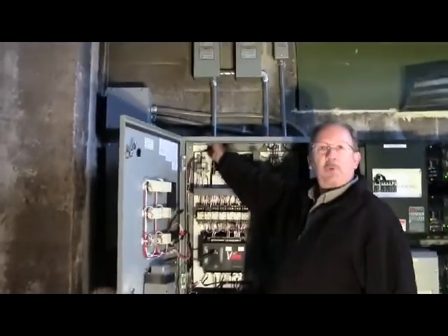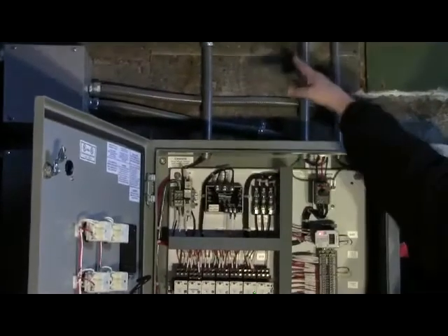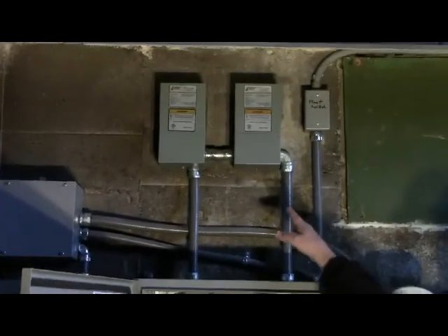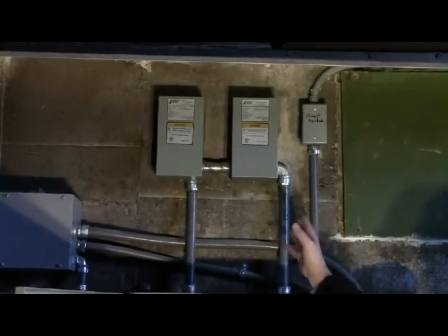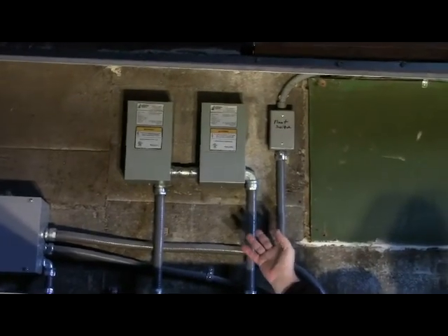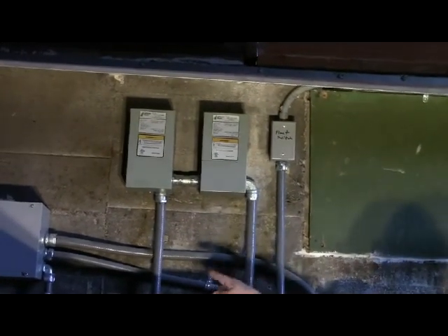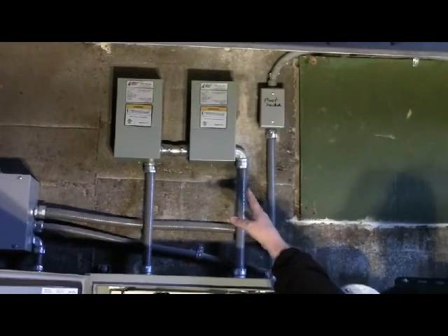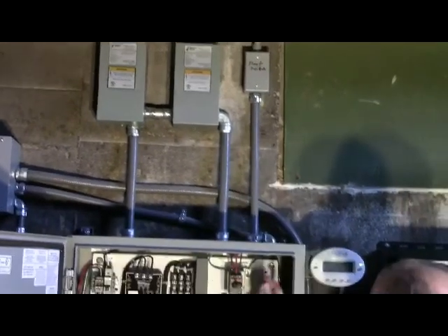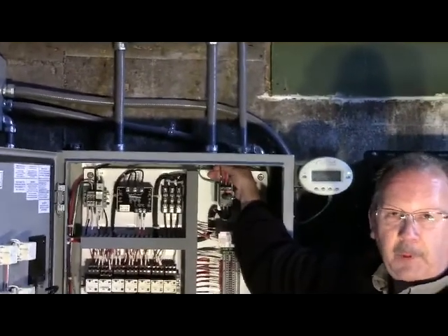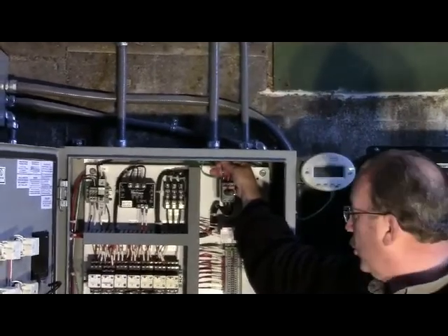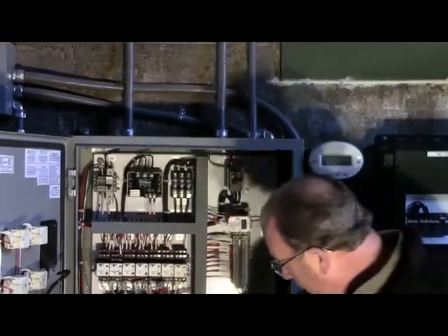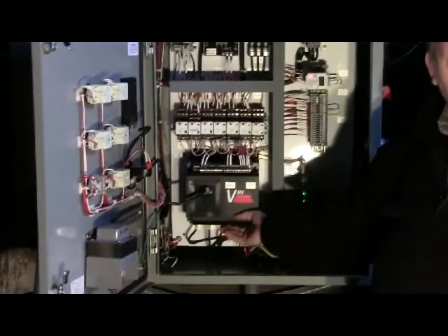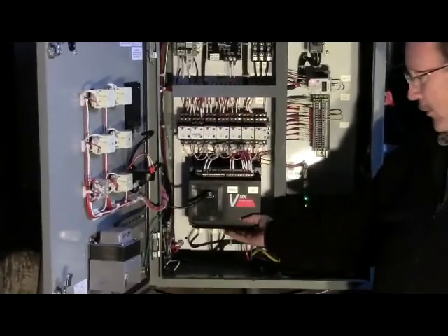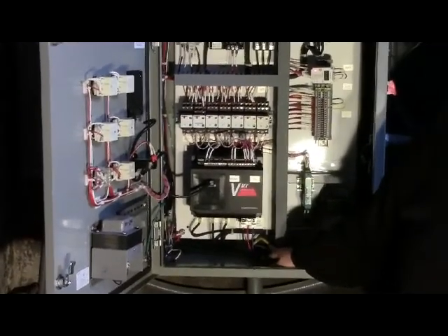That's a black, red, and a blue. We're going up to my buck-boost transformers, and here I chose to use an open delta system because that's all I needed, and the transformers were plenty big. The 208 comes up, goes through the transformers, comes back down here to the main disconnect in this pump panel at 230 volts. This then goes down and feeds my drive to start the pump at 230 volts and feeds 230 volts to my pump.